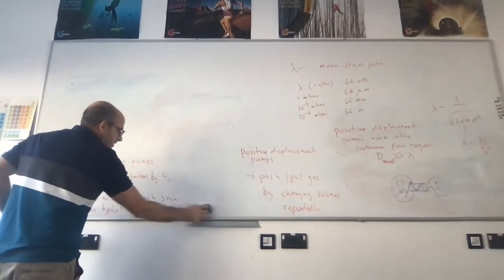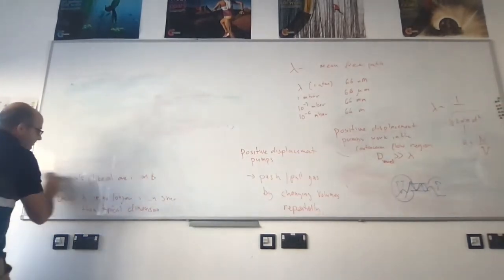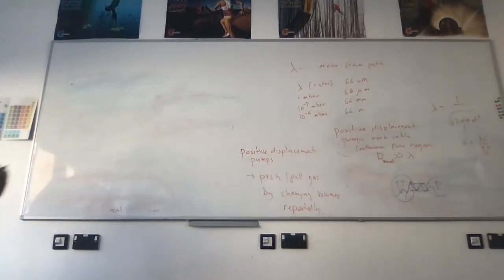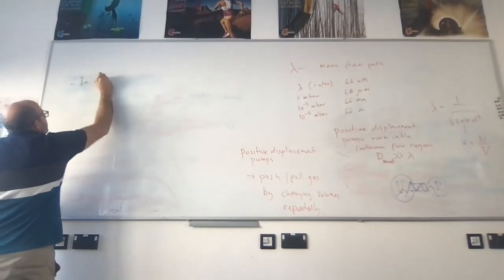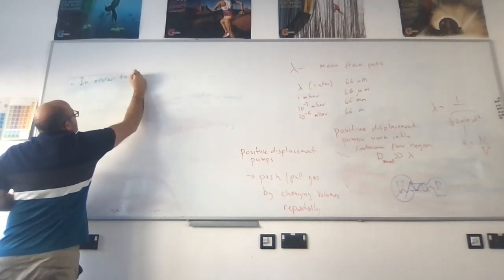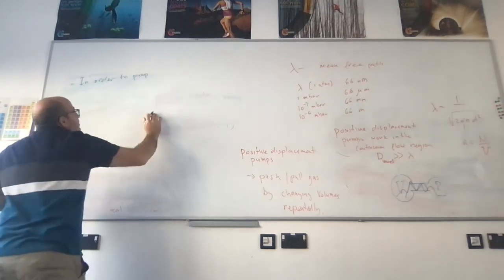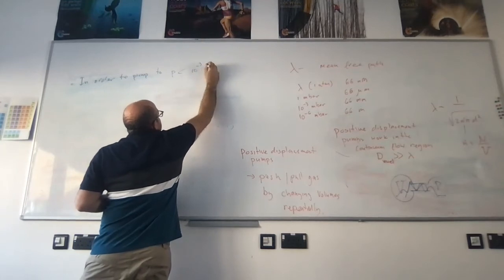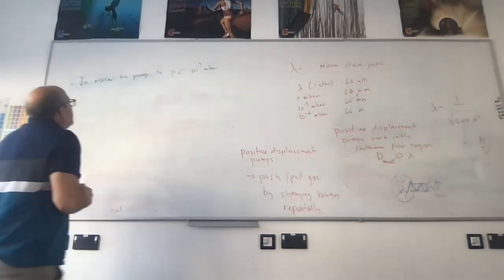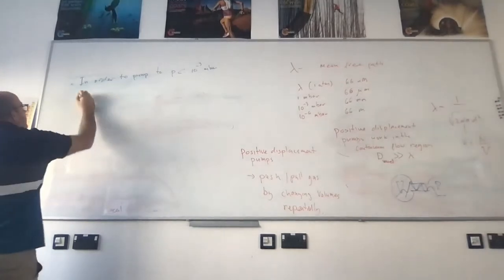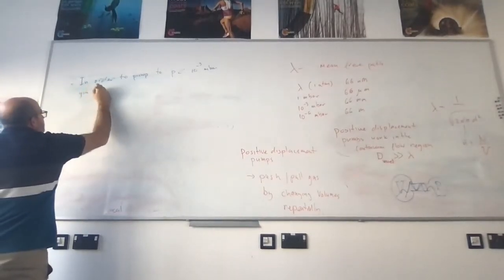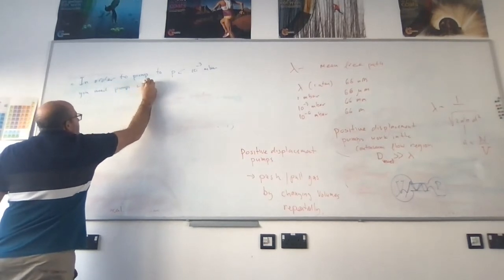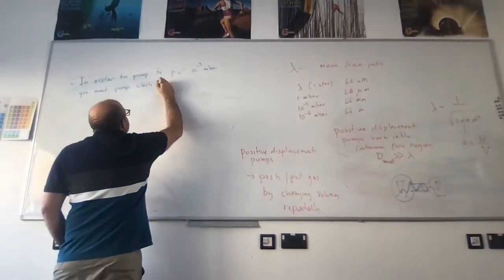So basically, in order to pump to pressures which are kind of smaller than 10 to the minus 3 millibars, and that's the unit that I happen to like, you need pumps which work in something which is called the molecular flow regime.